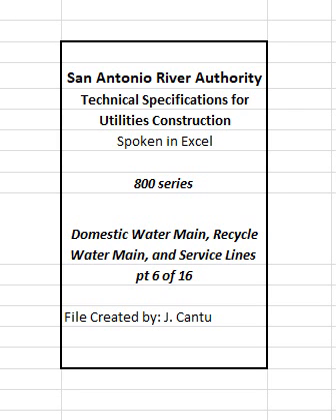A536 grade 65-45-12. The inside face or contact surface of the band shall be of sufficient width to incorporate machined non-directionally sensitive serrations to grip the outside circumference of the pipe. The serrations shall provide full 360 degrees contact and maintain pipe roundness and avoid any points of localized stress.